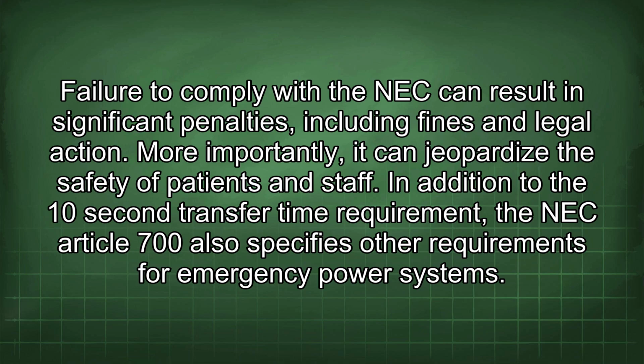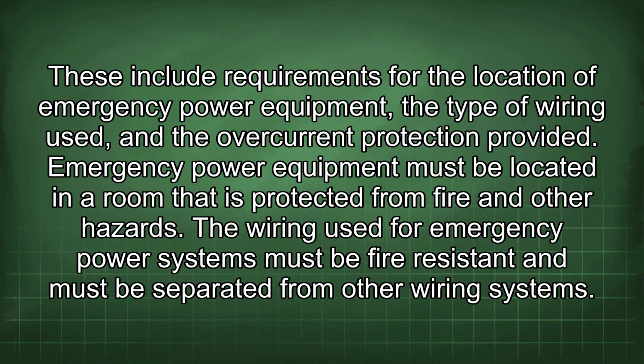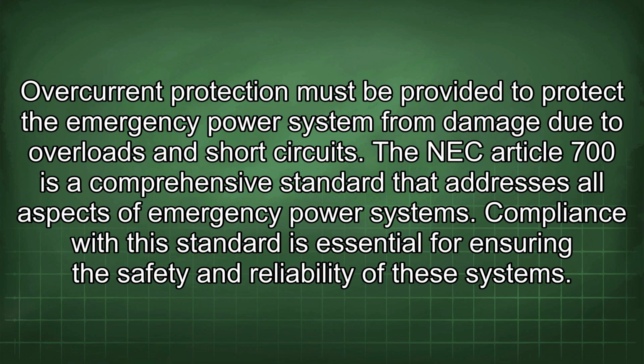In addition to the 10-second transfer time requirement, the NEC Article 700 also specifies other requirements for emergency power systems. These include requirements for the location of emergency power equipment, the type of wiring used, and the overcurrent protection provided. Emergency power equipment must be located in a room that is protected from fire and other hazards. The wiring used for emergency power systems must be fire resistant and must be separated from other wiring systems. Overcurrent protection must be provided to protect the emergency power system from damage due to overloads and short circuits.